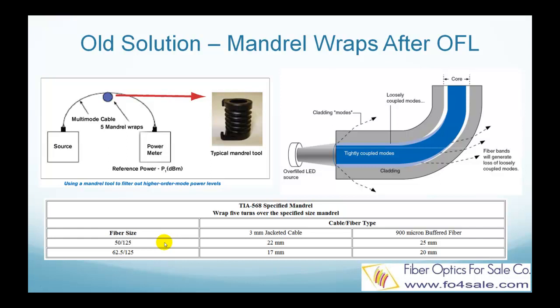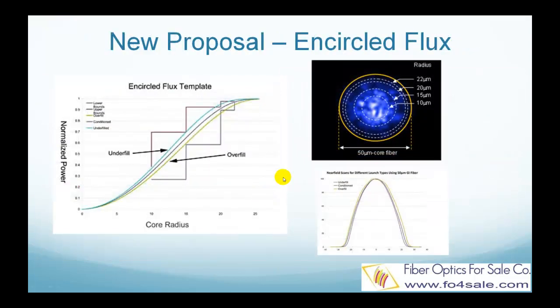This method is good for overfilled LED launch conditions up to 622 Mbps. But after that, VCSEL lasers are used instead of traditional LEDs. So people found out that this test is not accurate enough for Gigabit Ethernet and 10 Gigabit Ethernet. In order to control the launch condition in real-world VCSEL lasers using Gigabit Ethernet and 10 Gigabit Ethernet, the new encircled flux template method was developed. This standard proposes a field condition with upper and lower limits in order to get consistent, realistic, and repeatable loss readings.